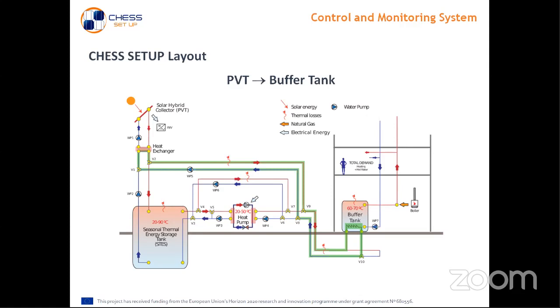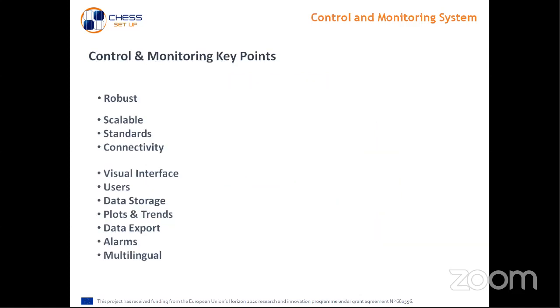Then we designed and implemented a control system that solves this problem and works autonomously. During the design, we decided it was very important that the resulting system be very robust. The heating of a building is not a matter of life or death, but the CHESS Setup is typically designed for large customers, so there might be many people depending on this system. So we wanted to make it as robust as possible, so that the main functionality—storing and delivering energy to the customer—never stops.